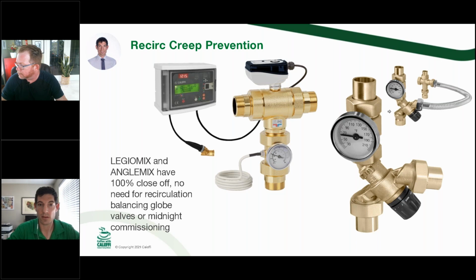These two Caleffi products, the LegioMix and then that AngleMix that has the angle pattern that's nice to put right on top of a water heater, that will actually close 100% the hot as well. So that's a thermostatic that can close the hot completely. The rest of the line of thermostatics, at least from our catalog, you will need to pipe to prevent that recirc creep if you're using a recirc pump. So those two don't require that midnight, what is the temperature coming back with zero load commissioning step that you'd have to do with a globe valve.